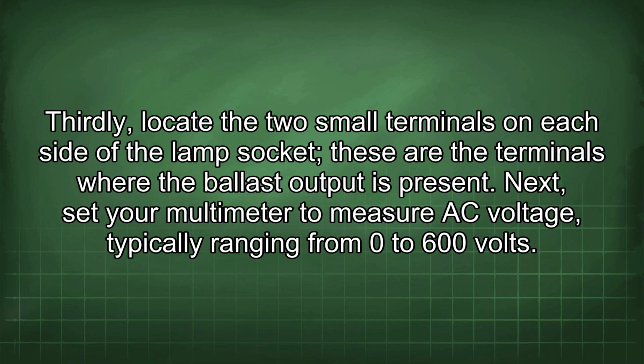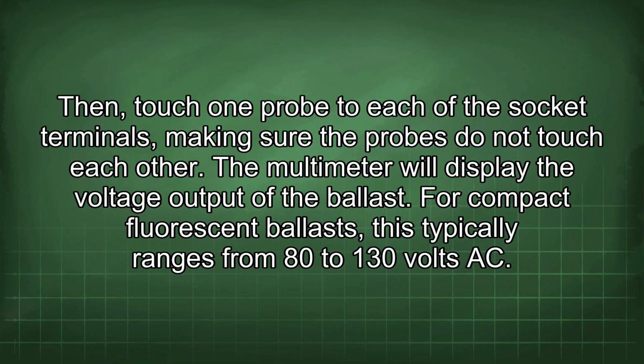Next, set your multimeter to measure AC voltage, typically ranging from 0 to 600 volts. Then touch one probe to each of the socket terminals, making sure the probes do not touch each other. The multimeter will display the voltage output of the ballast. For compact fluorescent ballasts, this typically ranges from 80 to 130 volts AC.